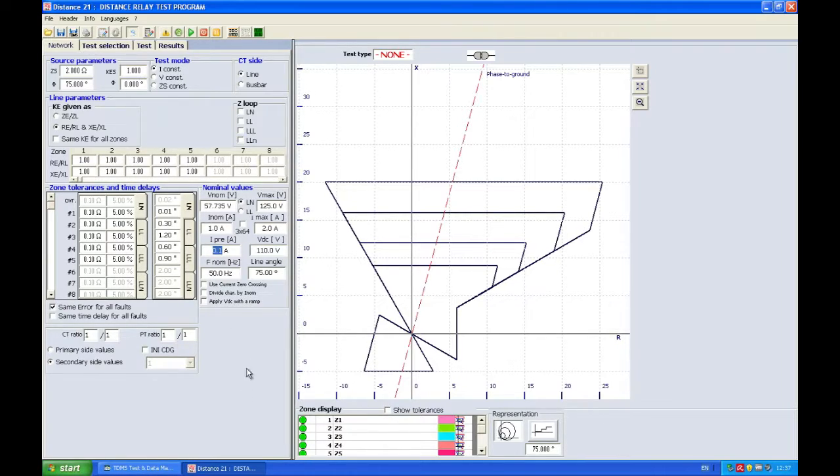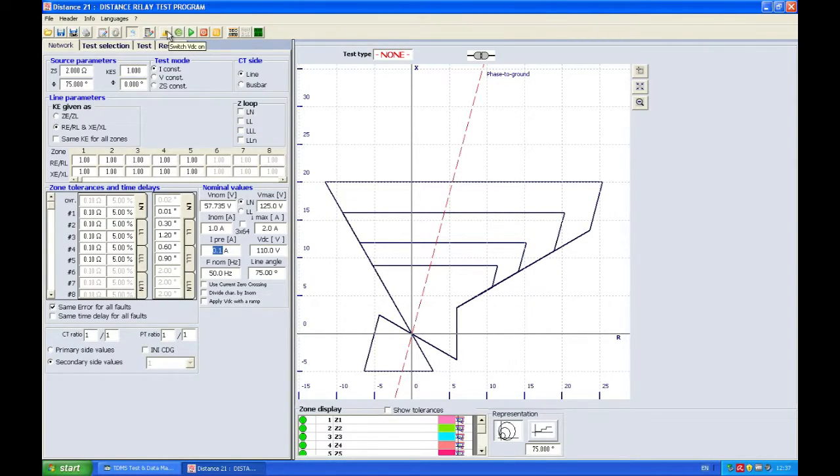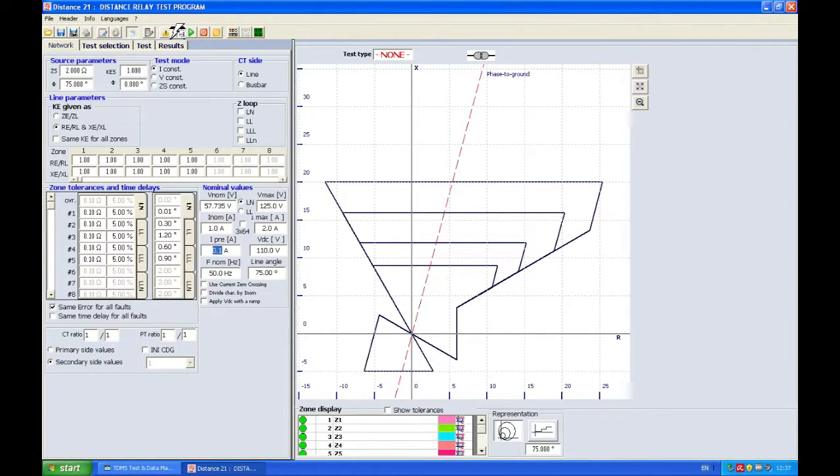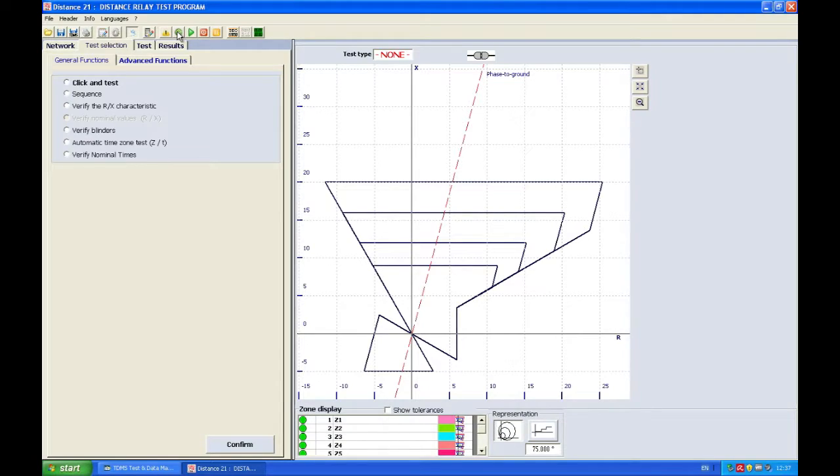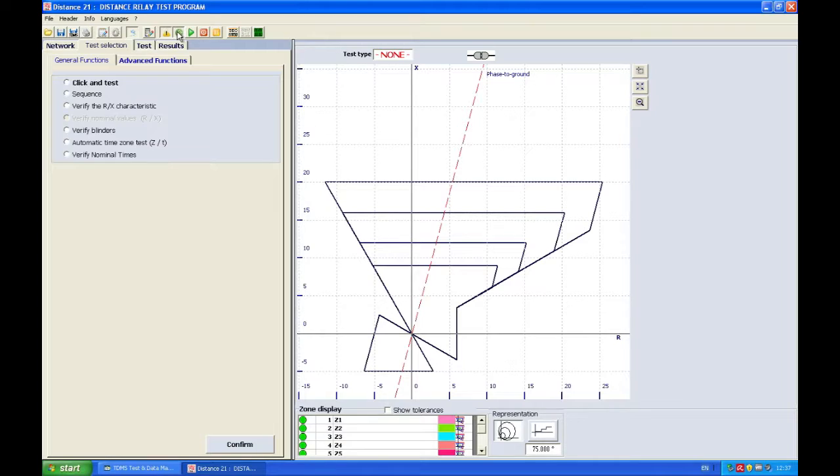The first step now will be generating prefault because I don't have to switch on the DC because I already did that before. Apply prefault and right now I'm looking at my relay and I see that the relay is measuring three times 57.7 volts and that the current is measuring three times 0.1 amp. Of course these are the prefault values which don't trip the relay and I'm going to do one basic test right now.